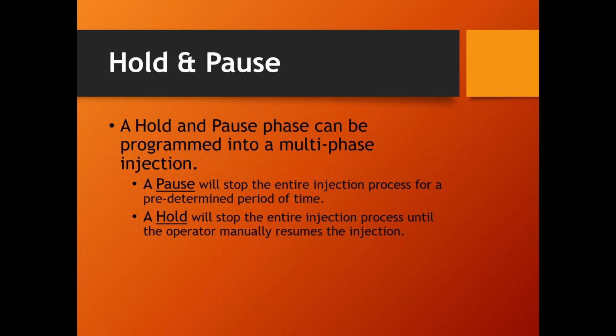So the difference between a hold and a pause is that with a hold, the injector doesn't start injecting again until the operator hits the button. With a pause, the operator doesn't have to hit the button. A pause is a specific length of time, then the system will automatically move on to phase 3. Yeah. So that's probably based on just the different procedures. Yes, absolutely. It's just whatever you're trying to achieve, fitting the image. That's why there are the 2 different.